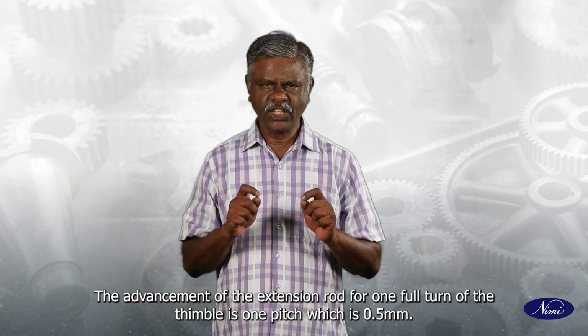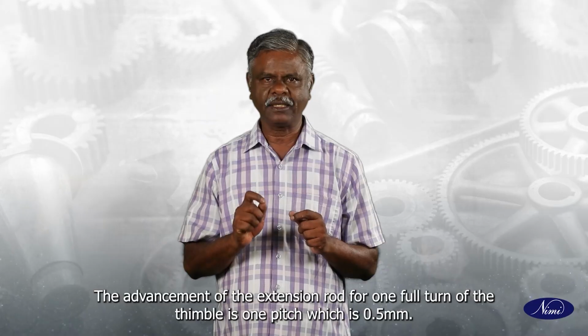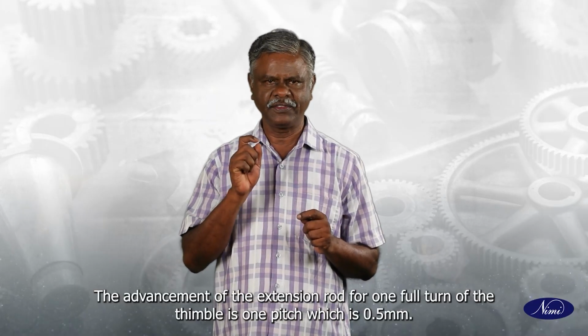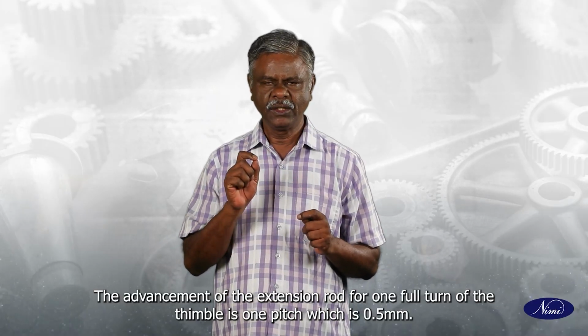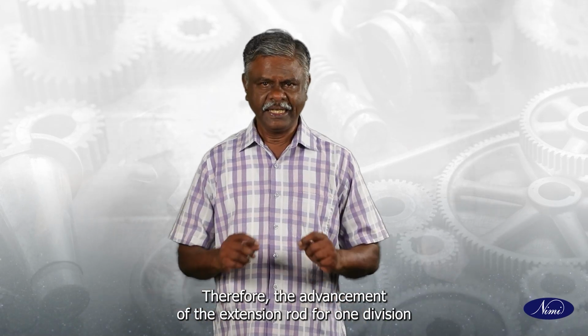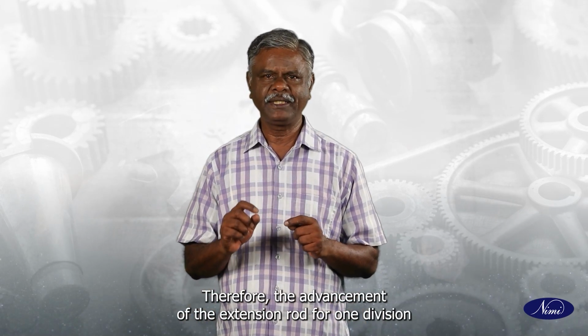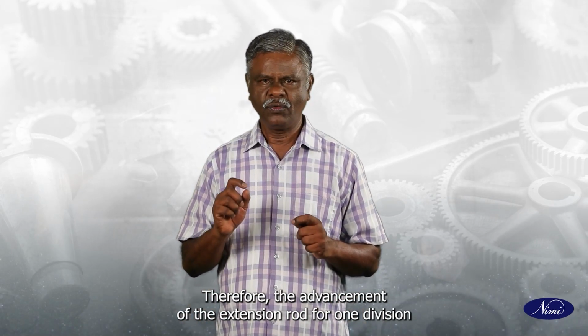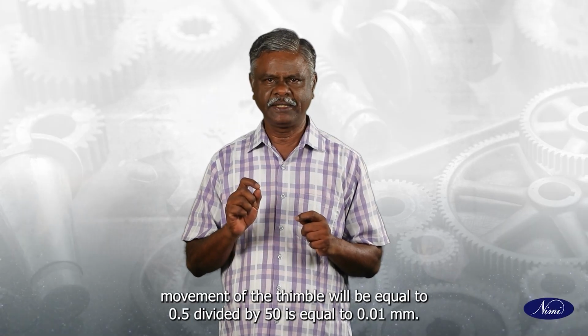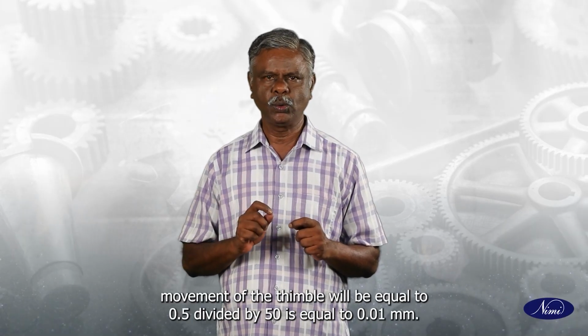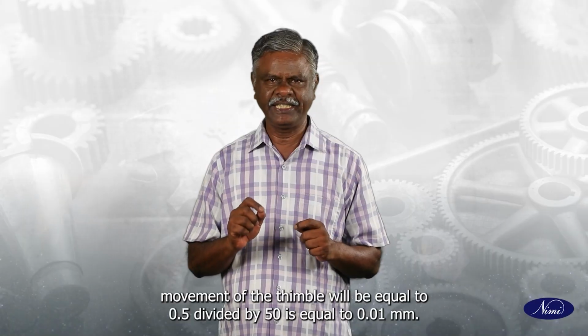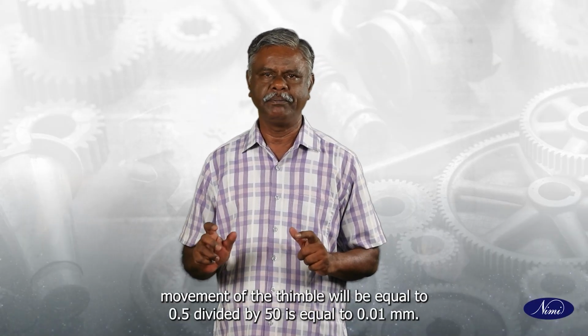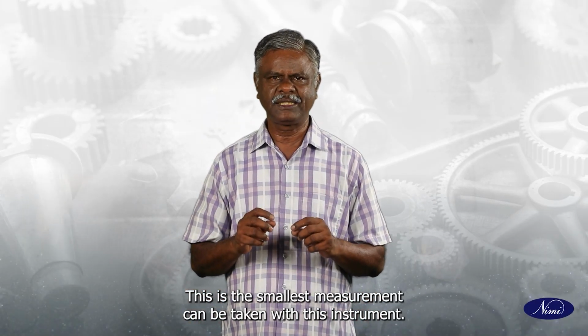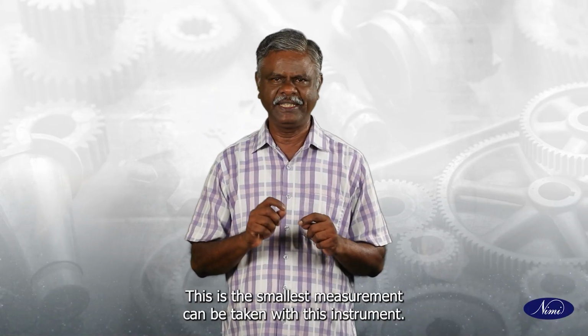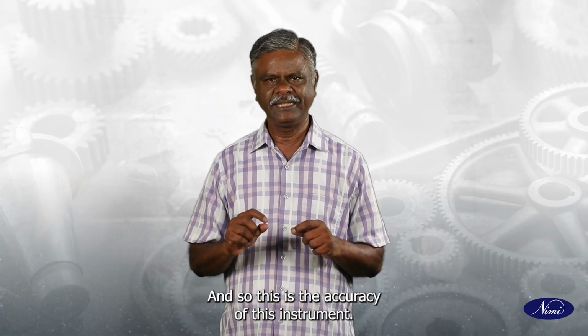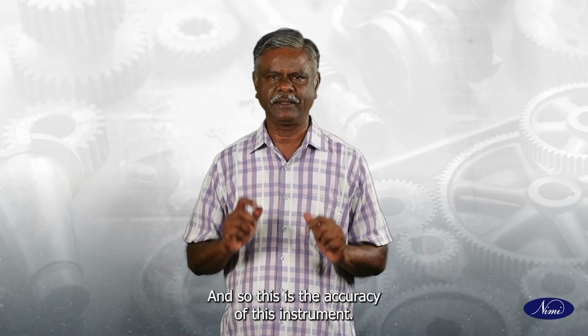The advancement of the extension rod for one full turn of the thimble is 1 pitch, which is 0.5 mm. Therefore, the advancement of the extension rod for one division movement of the thimble will be equal to 0.5 divided by 50 is equal to 0.01 mm. This is the smallest measurement can be taken with this instrument, and so this is the accuracy of this instrument.